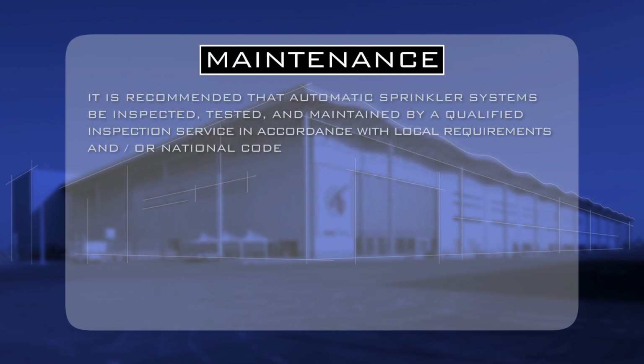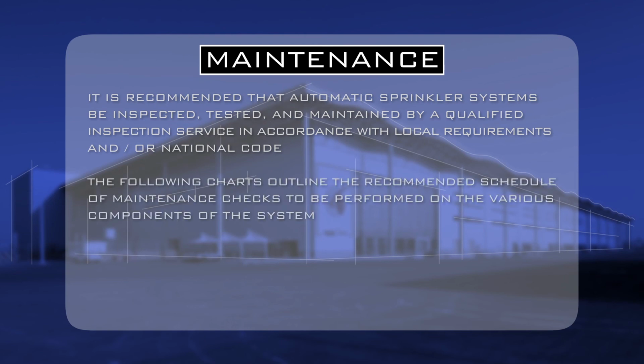It is recommended that automatic sprinkler systems be inspected, tested and maintained by a qualified inspection service in accordance with local requirements and/or national code. The following charts outline the recommended schedule of maintenance checks to be performed on the various components of the system.